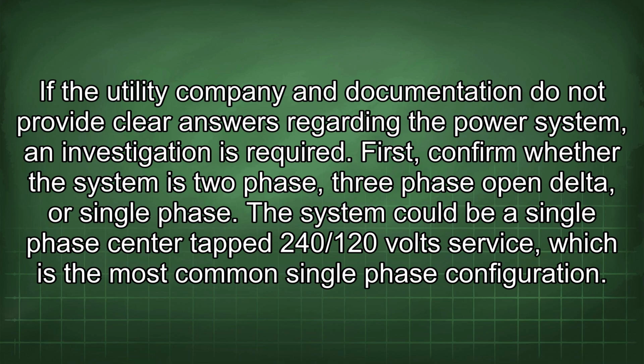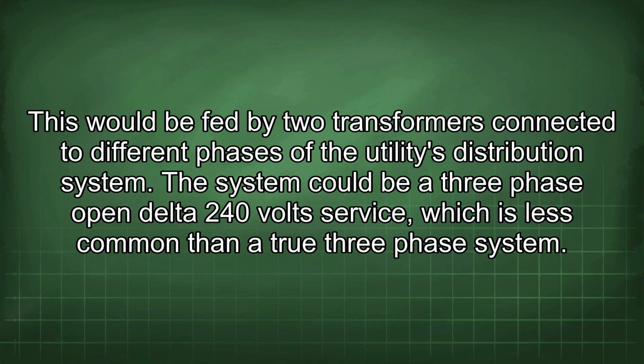First, confirm whether the system is two-phase, three-phase open delta, or single-phase. The system could be a single-phase center-tap 240/120 volt service, which is the most common single-phase configuration. This would be fed by two transformers connected to different phases of the utility's distribution system.